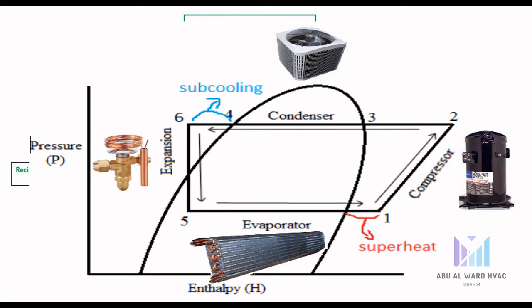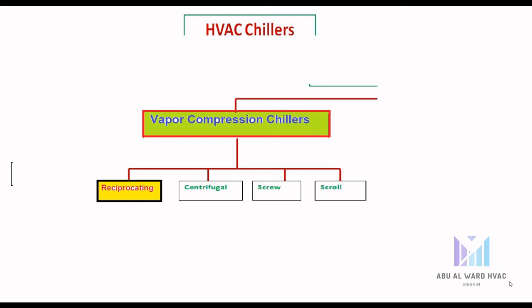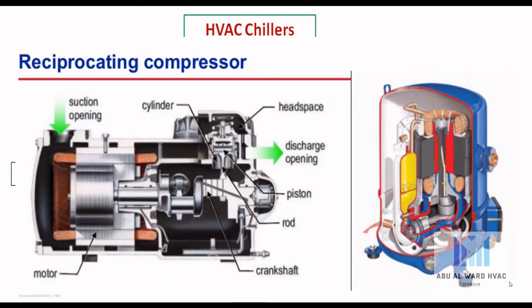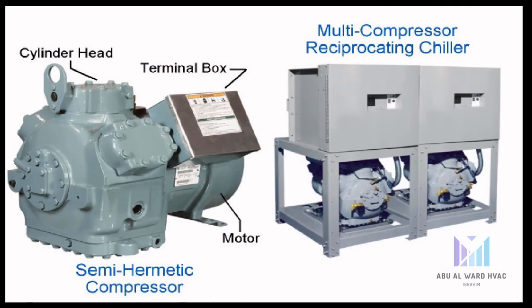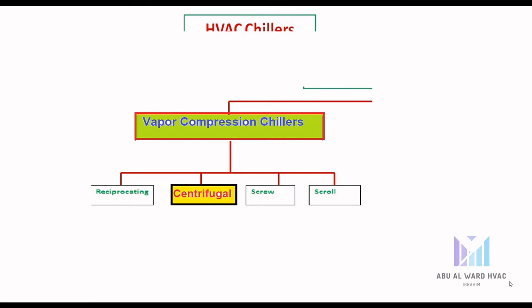The vapor compression circuit includes the following components: compressor, condenser, expansion valve, and evaporator. For vapor compression chillers, the reciprocating type: reciprocating compressors, like a reciprocating engine, have pistons, rods, and discharge and intake valves. Compression is achieved by trapping a fixed amount of refrigerant gas in a chamber, making them positive displacement type compressors.